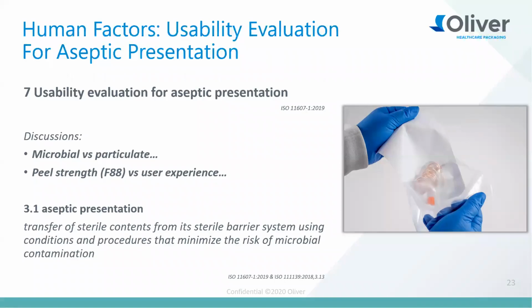The two most influential design features of packaging for the user are things like the width of the seal. You can have the exact same seal strength in F88, but if you change the width of the seal, it changes the user's experience significantly. Pouches and other packaging configurations also have chevron designs and corner peel designs, all designed to make opening easier and help the user experience be better. So peel strength is not the number one focus.